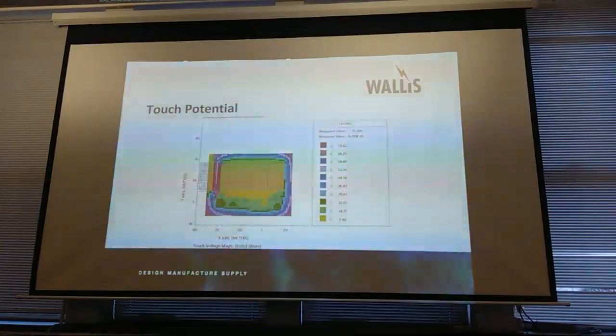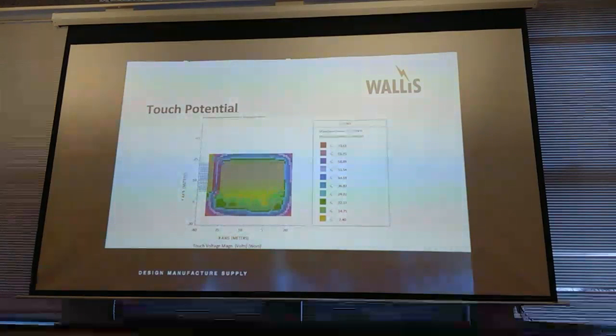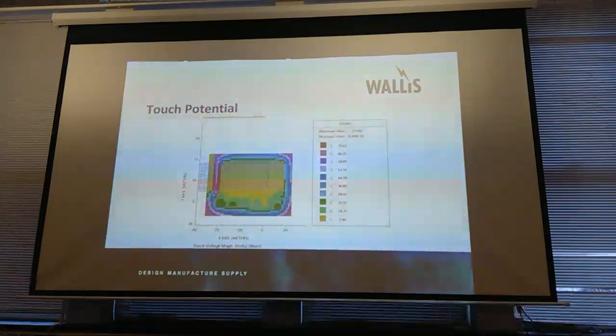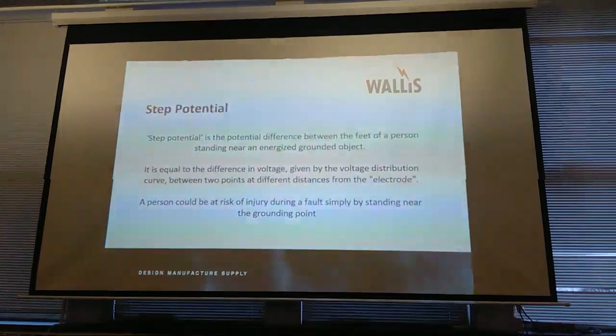Again, going back to the site, touch voltages do vary across the site. Because we've got that very nice mesh in the ground there, and it's all the rebars all connected together, it's fantastic. But as you come out, towards the edge of the site, towards the edge of the earth system, you can actually see the touch potentials are starting to creep up. So that's something you have to be a little bit careful of.